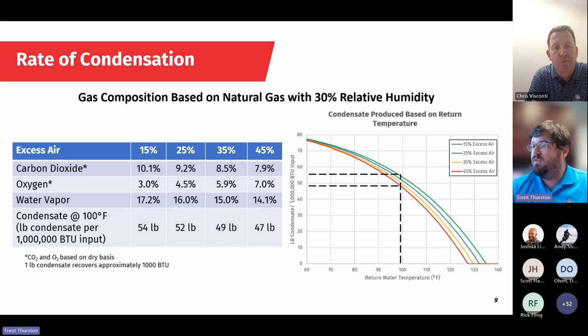So a 15% excess air burner, like what we can use in the Cheyenne, will be slightly condensing. Potentially a higher excess air burner would be not condensing at all and still stuck at the conventional boiler efficiencies. One thing to note on this is that 1 pound of condensate recovers about 1,000 BTUs. So with our example here at 100-degree return water, 15% excess air will recover 5.4% efficiency with the 54 pounds we have. The higher excess air potentially just gets 47 pounds, which gives only 4.7% efficiency. Now, yes, this is a good gain, but 4.7% is not achieving all it can do with the full aspect of a condensing boiler.